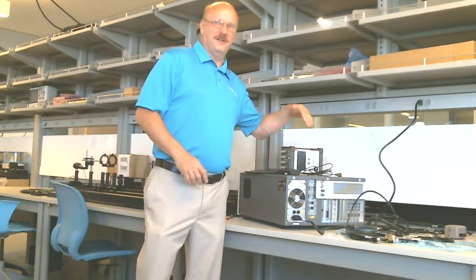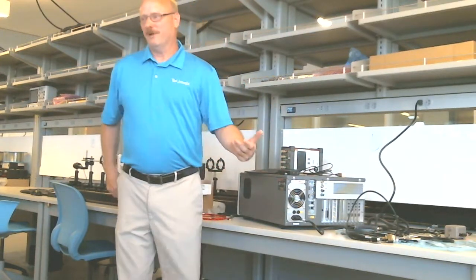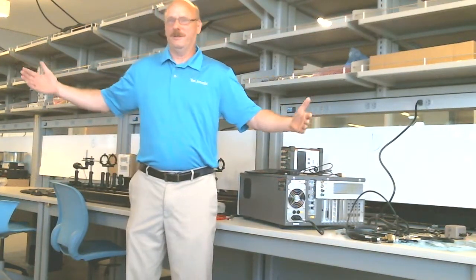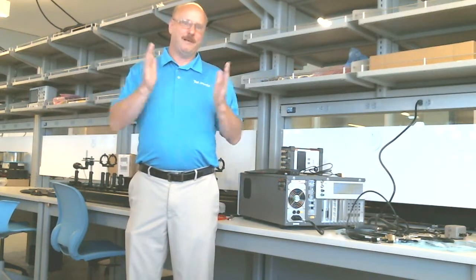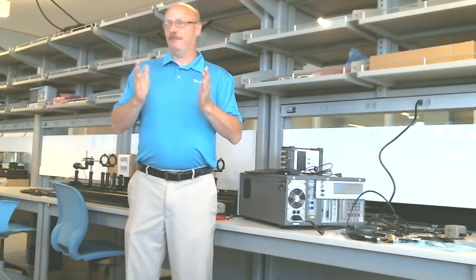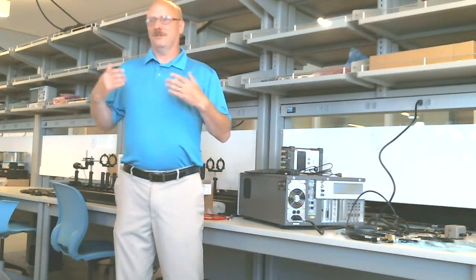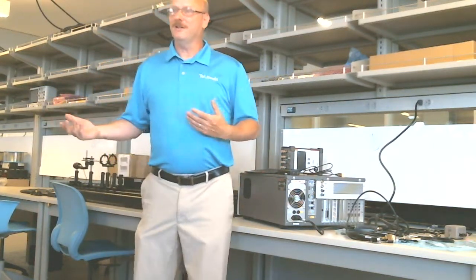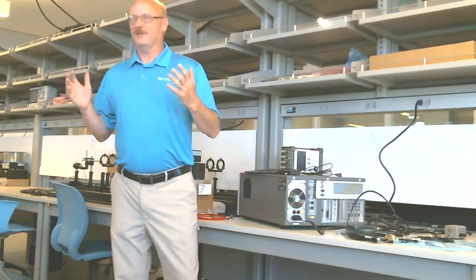everything you tack on to this instrument degrades your measurement capability, including your cable length. So keeping those cables short is absolutely key. Because you've got capacitance per foot of the cable. It's going to slow down your measurement capability. You're going to have leakage. You have all those things you're going to have to deal with.